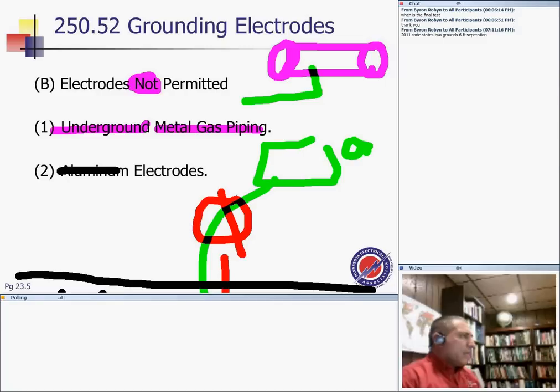And aluminum, the reason why we don't use aluminum, I hope you understand, is that you won't be able to find it after a couple of years. If you use aluminum underground, corrosion is very severe, and you're not going to find that aluminum after a while. It's gone. These are the only two restrictions, where you can't use a metallic object. It's a metallic object in direct contact with Mother Earth, but you are not supposed to use it as an electrode system.